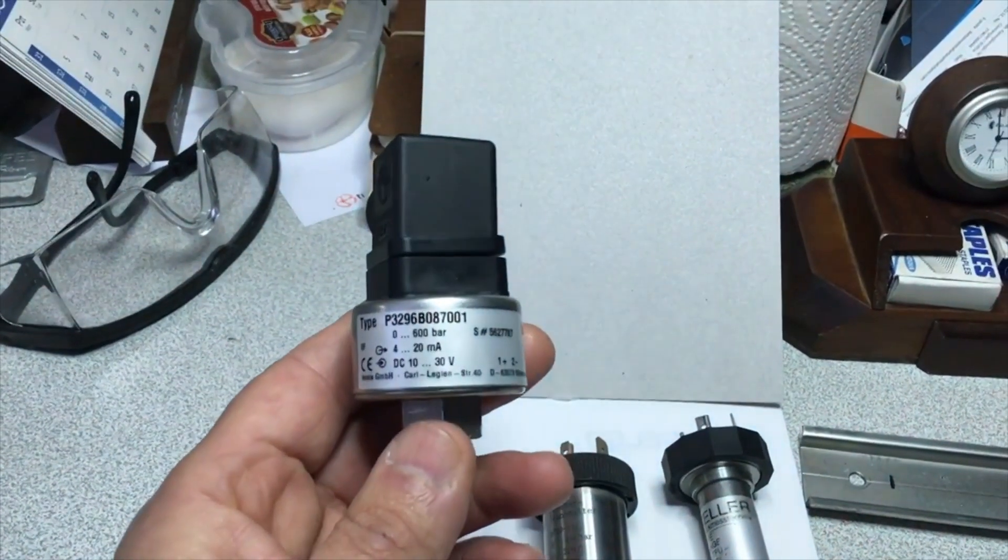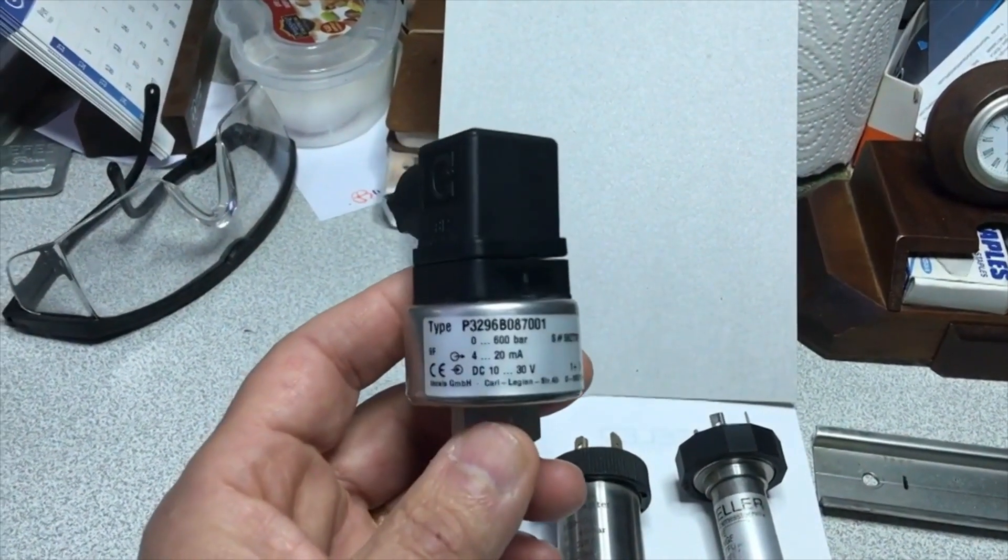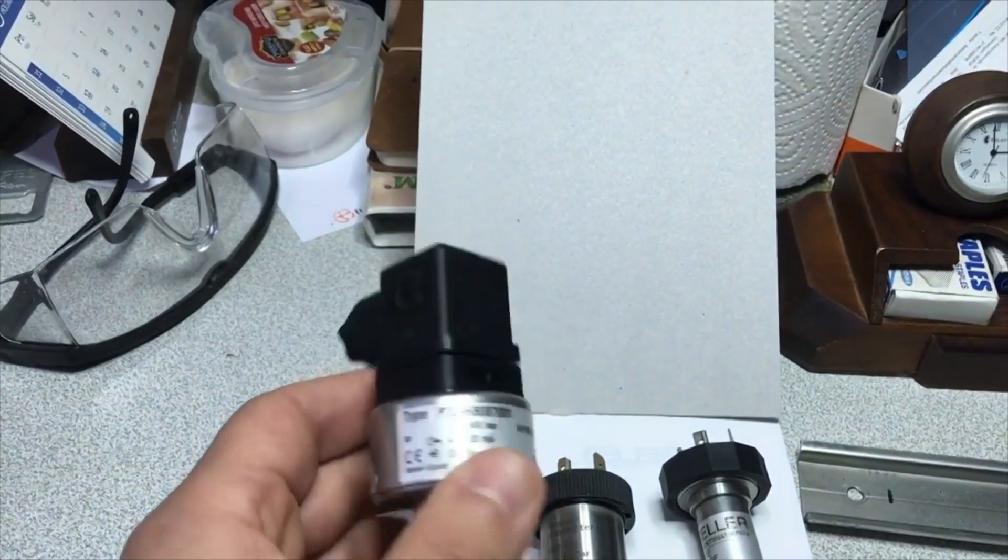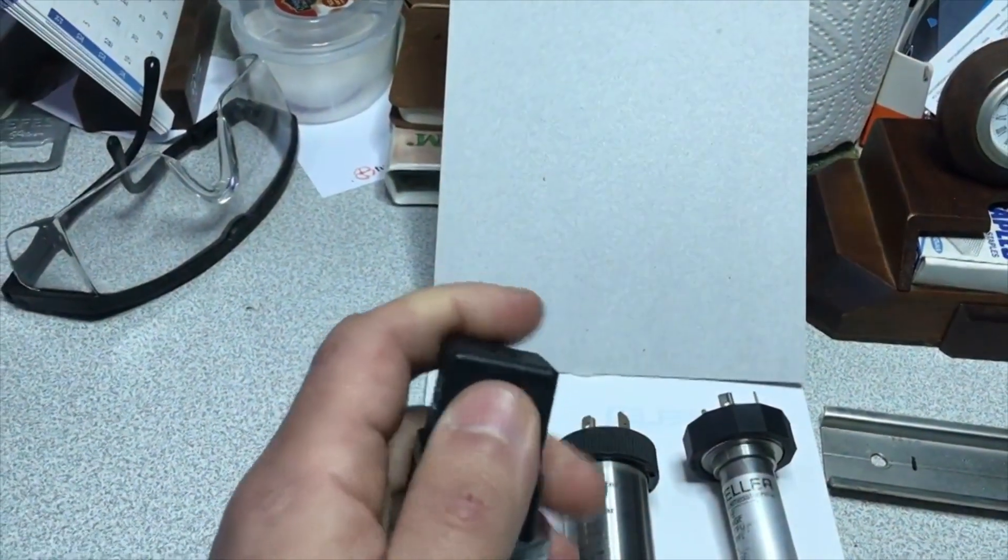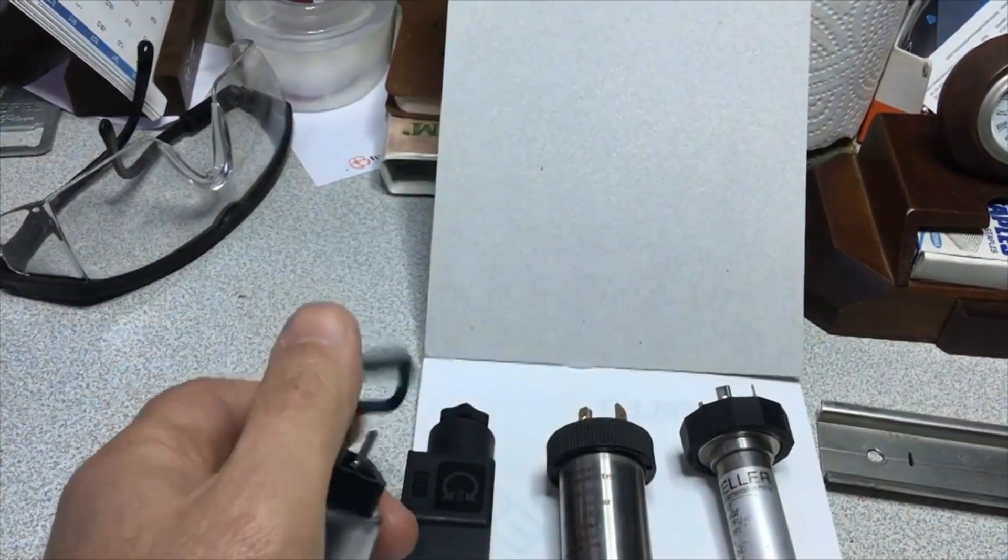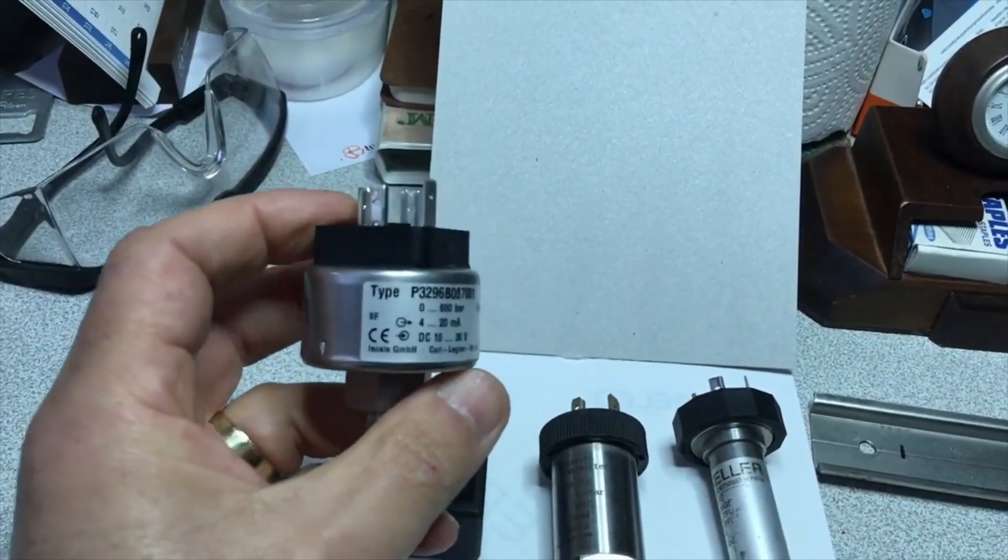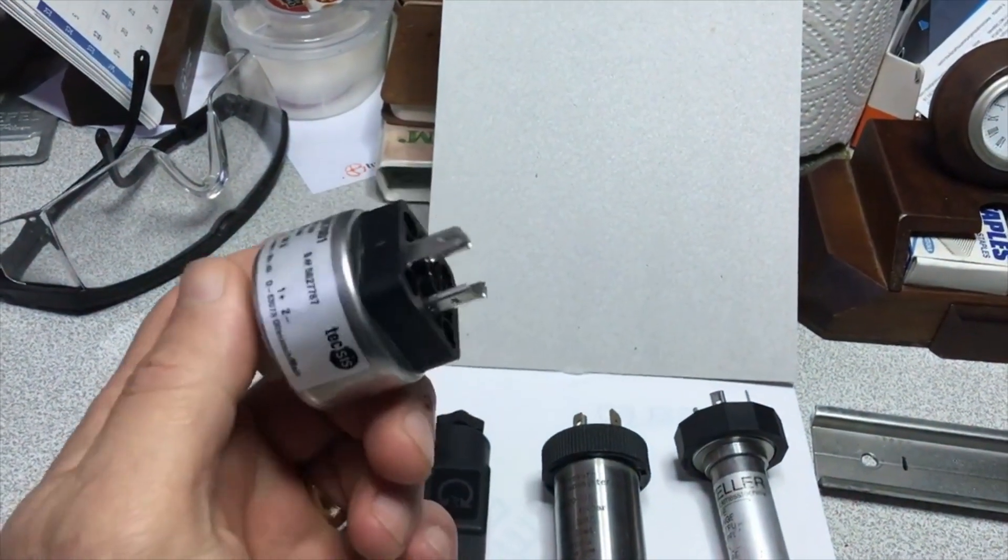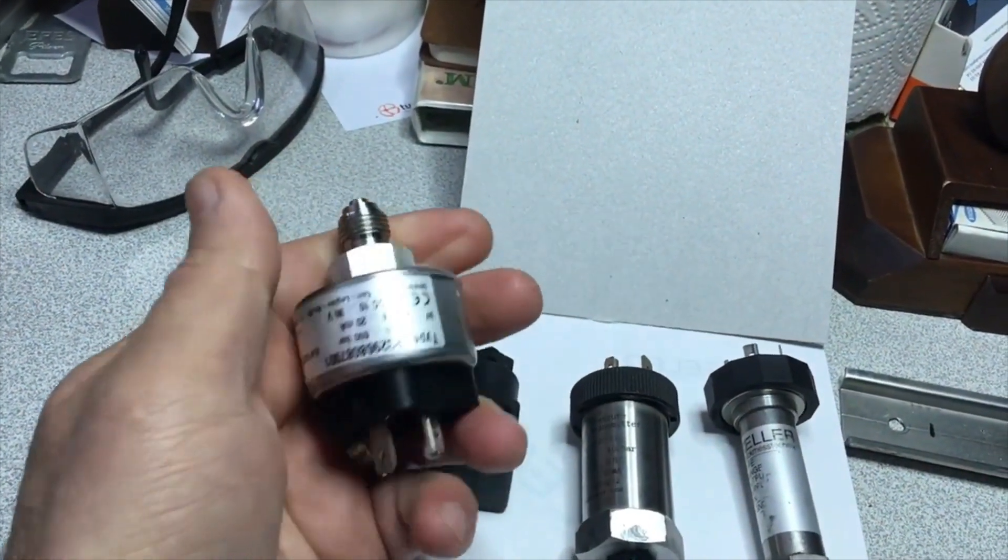The meaning of the output current is that when the pressure applied to our sensor is 0 bar, we will be able to output 4 milliamperes, and when the system pressure reaches 600 bars, the same sensors will give us 20 milliamps output. These sensors are also available with 0 to 10 volt output and 0 to 20 milliamp output.